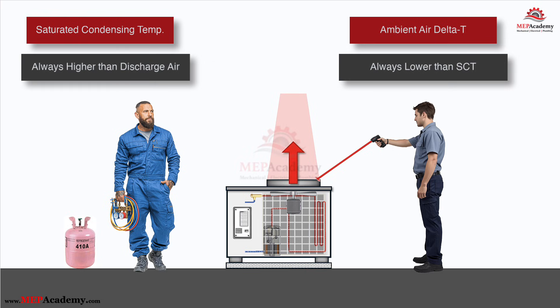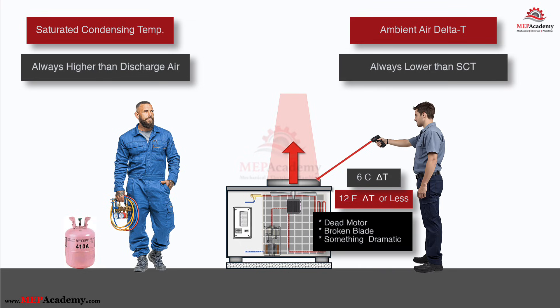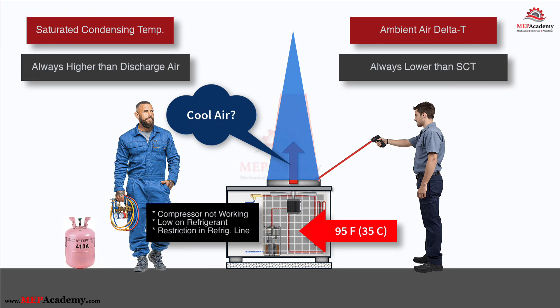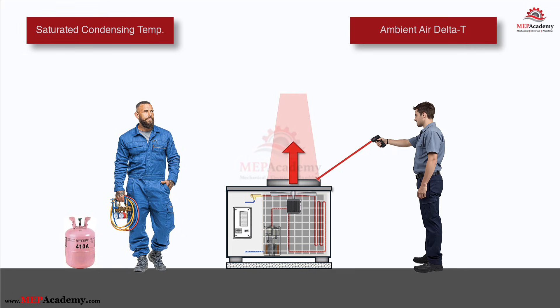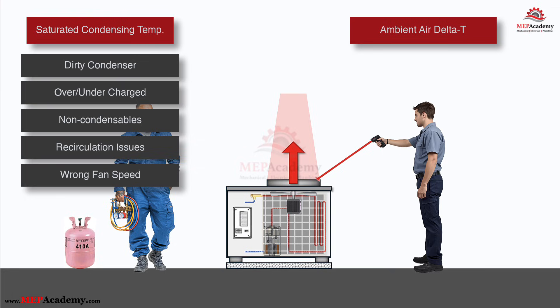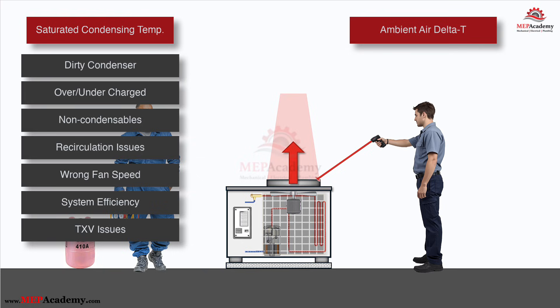Air delta T is great for two things: gross airflow problems — if the air rises 12°F or less, the fan is barely moving air; dead motor, broken blade, something dramatic — and as a quick sanity check that the system is doing something. If the discharge air is cool on a 95°F day, you instantly know the compressor isn't running or you're critically low on charge. Anything more subtle and air delta T lies to you. Real condenser TD tells you the actual health of the high side: dirty or blocked condenser coil, overcharge, undercharge, non-condensibles, recirculation, wrong fan speed on a variable speed unit, and whether a high efficiency unit with a big coil is running at its designed 15 to 18°F temperature difference. Air delta T can't see any of that reliably because coil design, fan speed, and airflow change the air rise even when the refrigerant temperature is perfect.